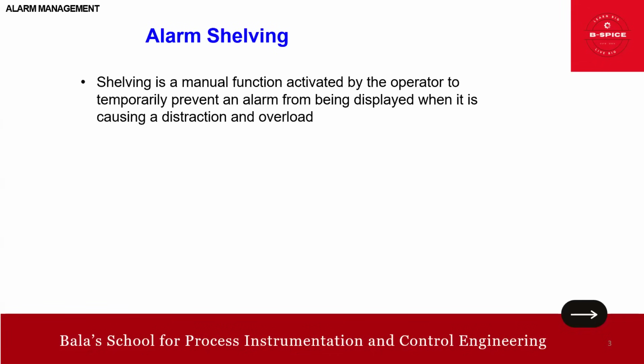So shelving is a very useful and powerful operational tool for the management of an alarm system because even with excellent system management, it is inevitable that some alarms will sometimes become temporarily of no value. This may be due to instrument malfunction or lack of maintenance or noise causing repeating alarms. So the usability of the alarm system is increased by allowing an operator to eliminate the distraction from alarms that the operator knows are of no operational relevance. Okay, so this is just an intro about alarm shelving.